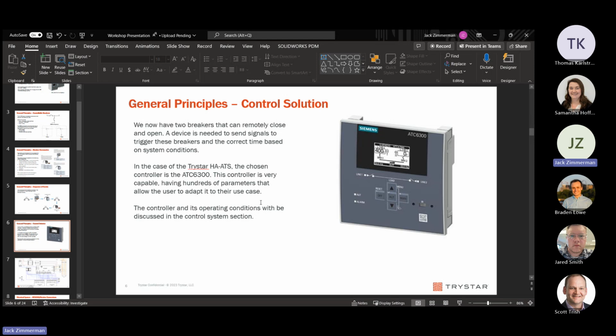The general builds, you could establish those parameters - all it is is changing the nominal voltage from 480 to 600 or 208. That's all managed by that device without going into the source code. Correct, so those high level parameters are just numbers in there. You still have to look at your percentages for tripping and that kind of thing, but I wouldn't say it's any more advanced than configuring a WO breaker or whatever.